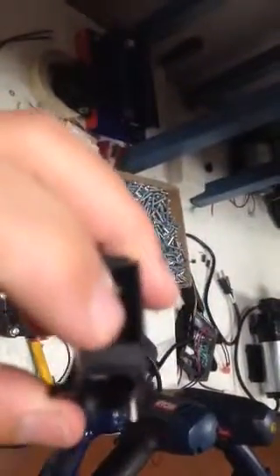The other thing I forgot to mention is we take a look at the prongs as well. If the prongs show some carbon tracking and some discoloring, graying color, that can start giving you a clue that maybe there's a moisture-related weakening or an overheating.